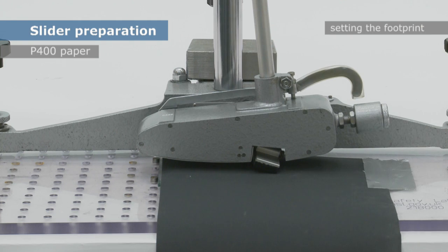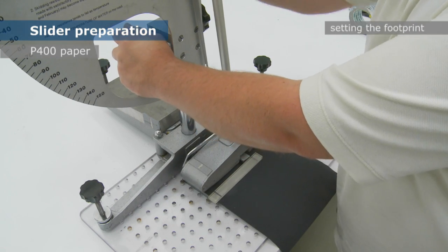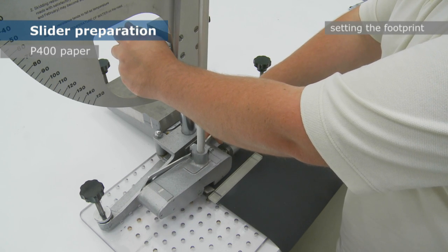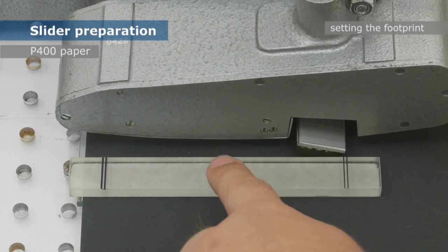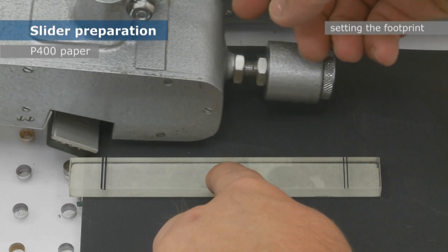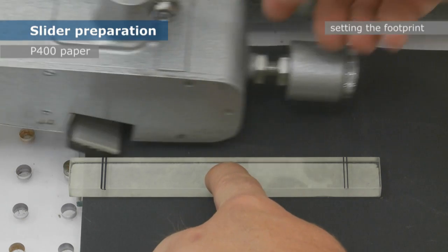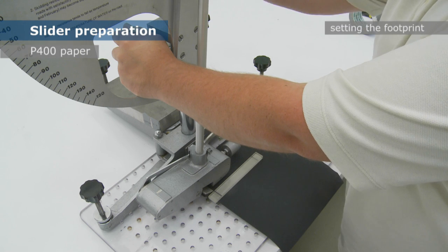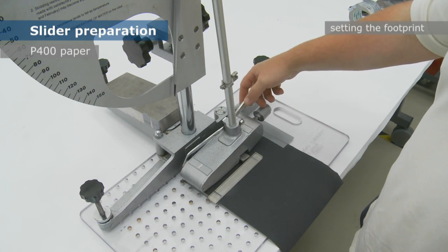The footprint is measured with the footprint ruler. The marks on the ruler are lined up with the trailing edge of the aluminium backing plate. This is an iterative process that relies on repetition with fine adjustments each time until the ideal position is found. Here, the means of adjustment is accessed via an opening in the scale plate, but the exact method of pendulum adjustment varies across the three machines.